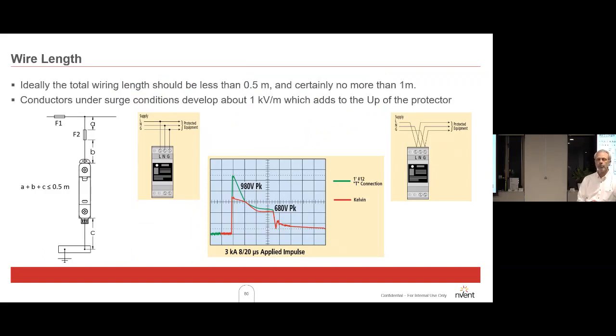Wire length is a very important factor though. You need to keep the wire length between here and your bus as short as possible. It can develop about 1,000 volts per meter. So if you've got 1 meter of wiring between your surge diverter and your supply, then you can lose 1,000. It makes the surge diverter 1,000 volts less effective. So if your surge diverter was going to let through 1,500 volts of the surge to your load in an ideal direct connected situation, and you have a 1 meter piece of connecting wire in there, it suddenly lets through 2,500 volts to the load.